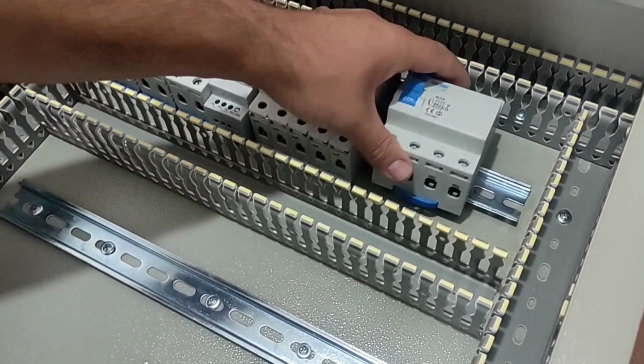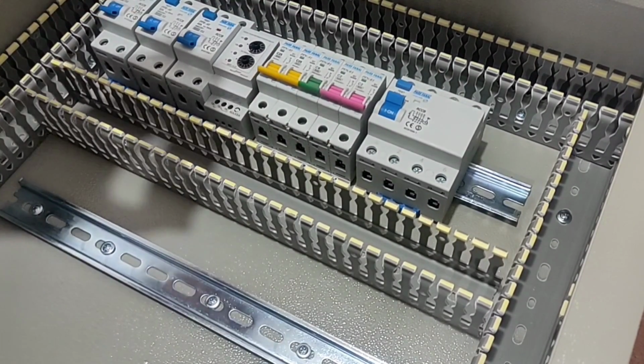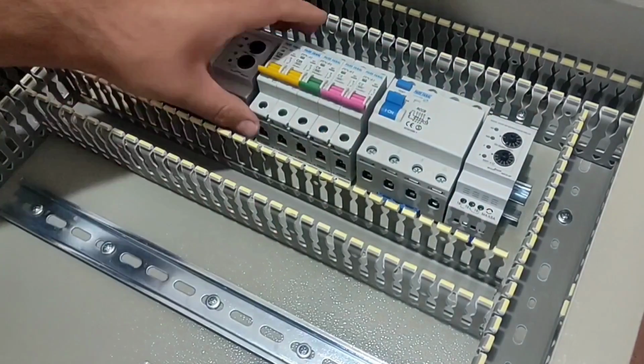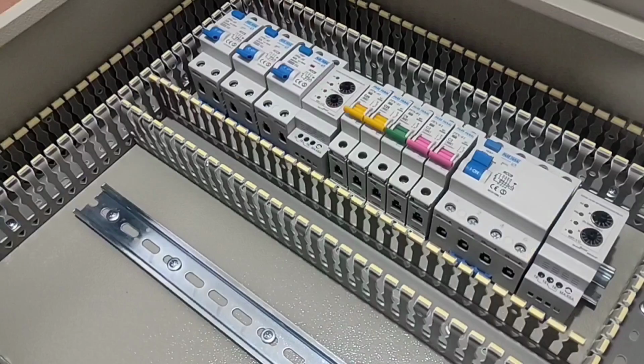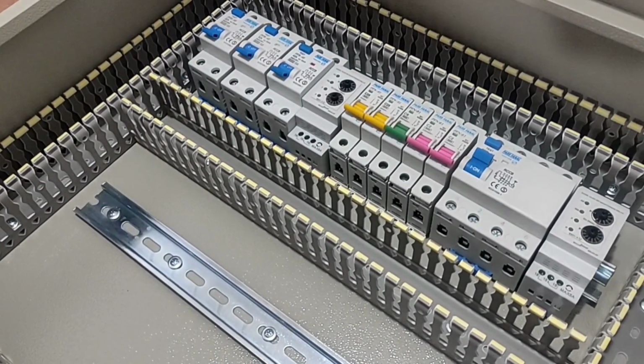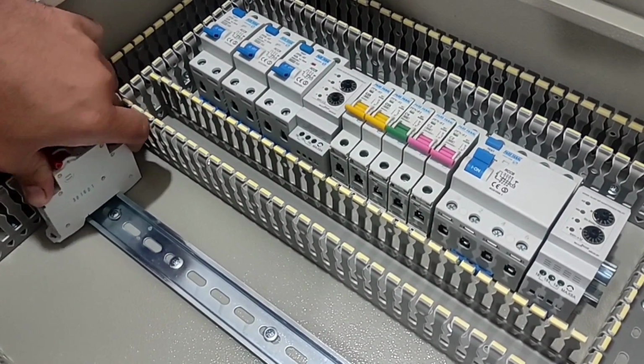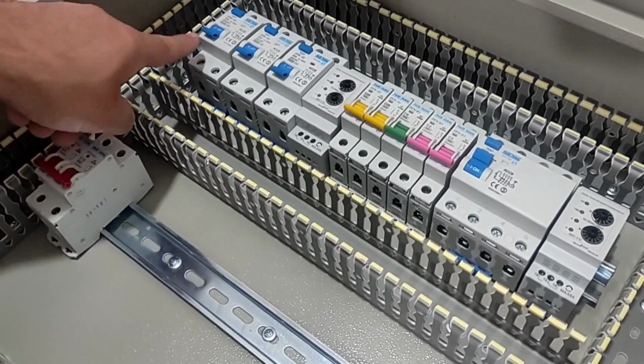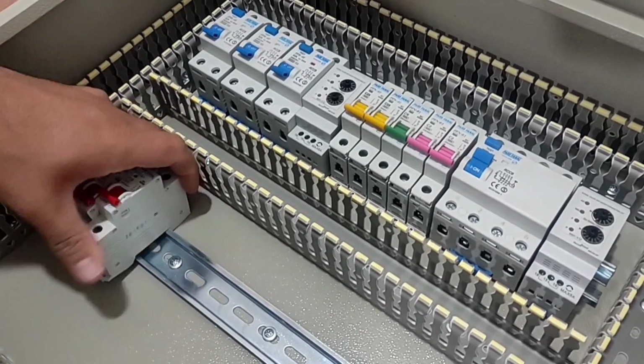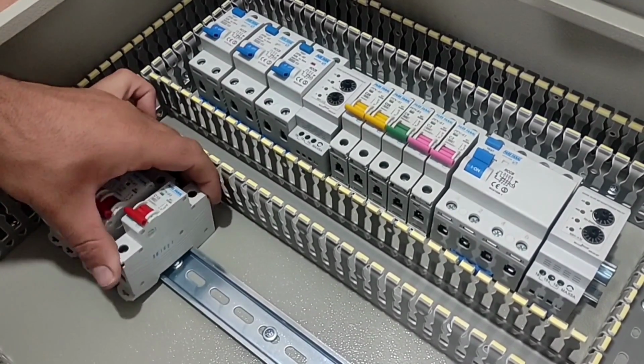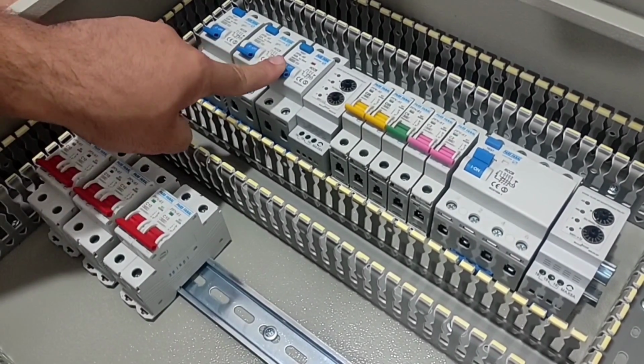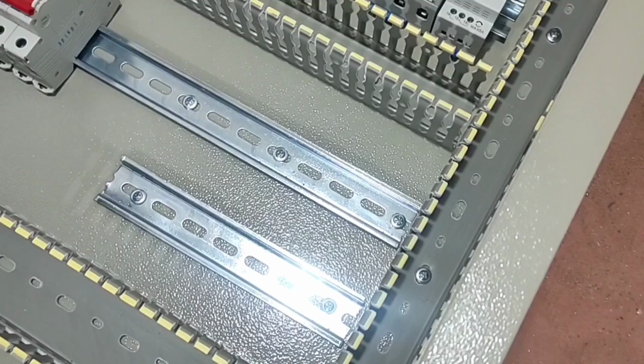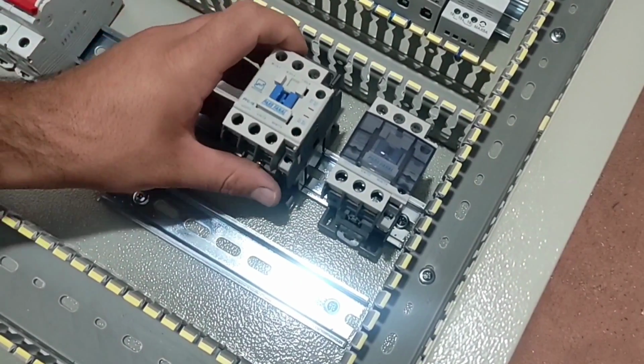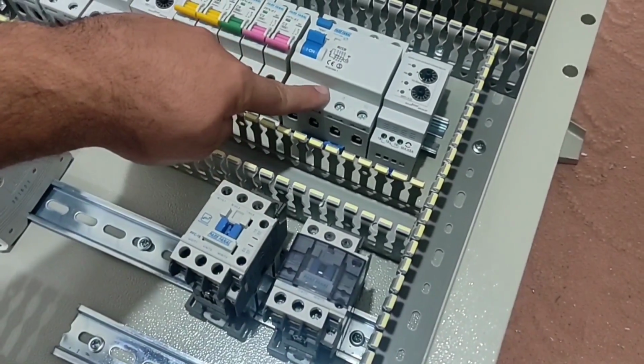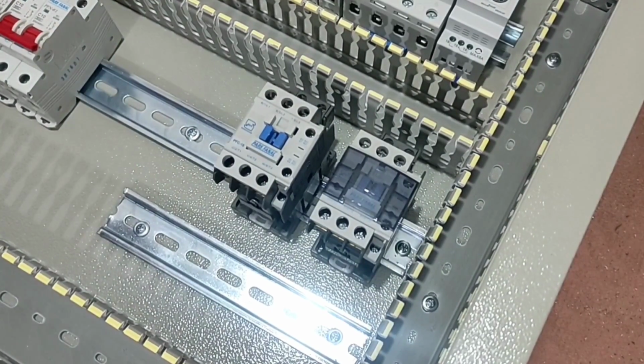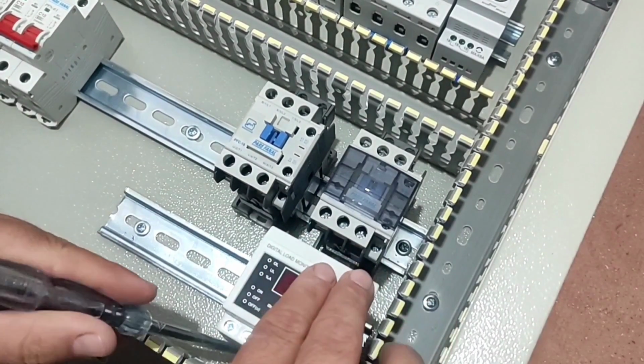We also install a 3-phase RCCB switch which is connected to 2 contactors. And for that, we install a phase controller to prevent phase loss in the electric motors. Now we install 2 miniature switches for each of the RCCB switches. Now we install 2 contactors for 3-phase electric motors. We also install a current controller for each electric motor to protect the electric motor from excess current.